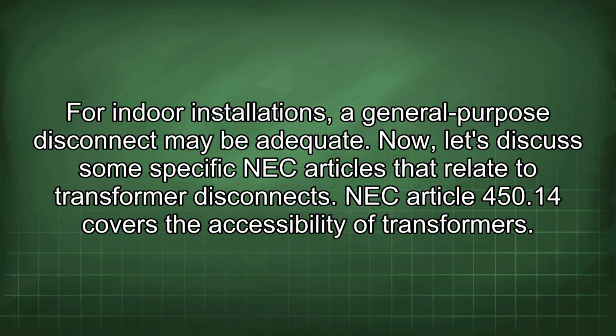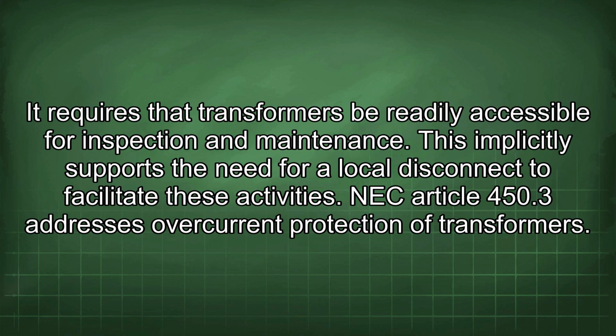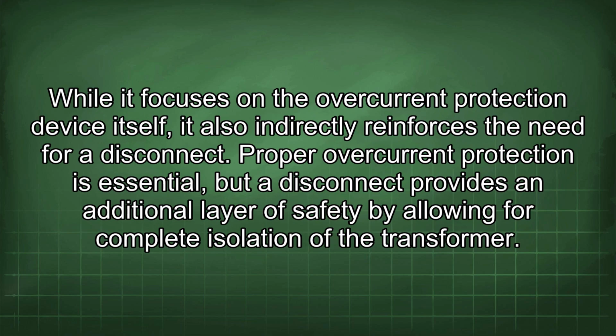Now let's discuss some specific NEC articles that relate to transformer disconnects. NEC Article 450.14 covers the accessibility of transformers. It requires that transformers be readily accessible for inspection and maintenance. This implicitly supports the need for a local disconnect to facilitate these activities. NEC Article 450.3 addresses overcurrent protection of transformers. While it focuses on the overcurrent protection device itself, it also indirectly reinforces the need for a disconnect. Proper overcurrent protection is essential, but a disconnect provides an additional layer of safety by allowing for complete isolation of the transformer.